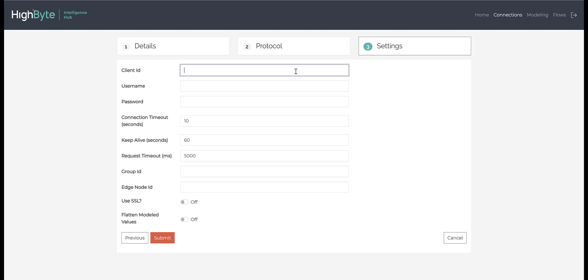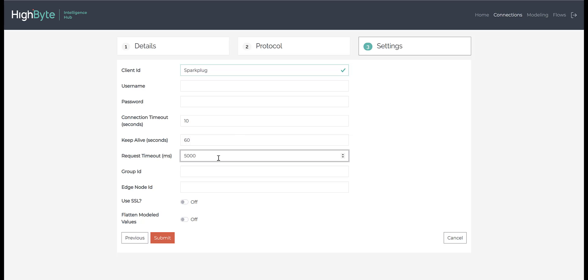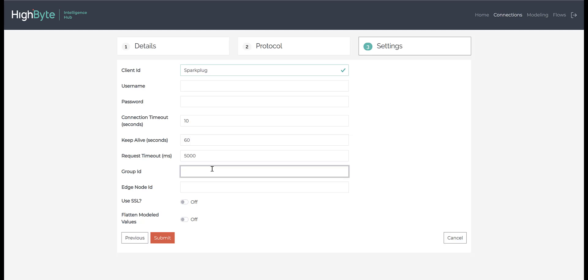Given Sparkplug leverages the MQTT standard, many of these settings probably look familiar to you. You will enter in a unique client ID to identify this connection, optionally set a username and password, and set the connection timeout and keep-alive settings. In addition to subscribing to Sparkplug information, the product also allows you to subscribe to Sparkplug data. By setting a request timeout, you can specify how long the HighByte Intelligence Hub should wait for subscribe data to arrive before timing out.